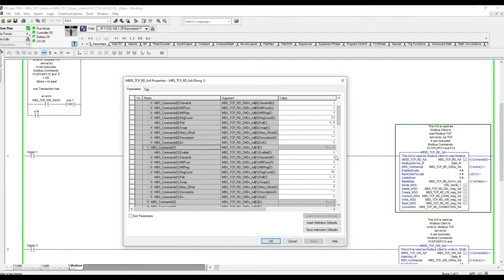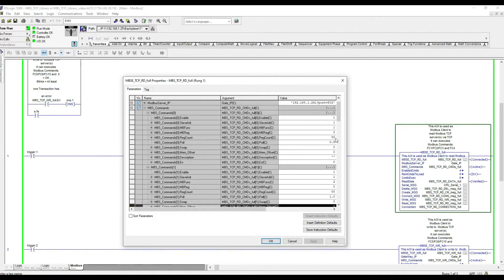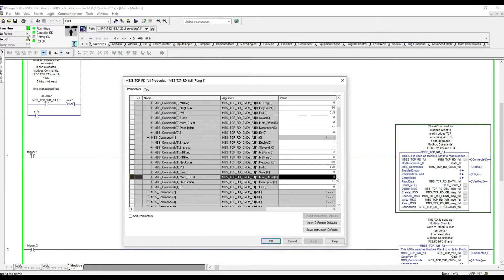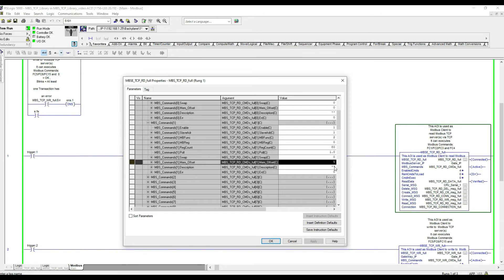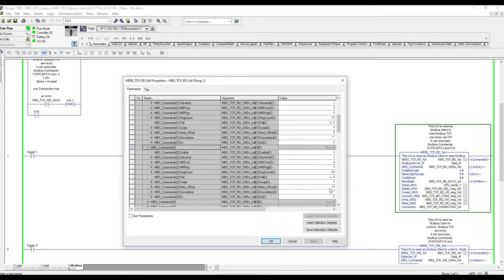The next command is function 2, reading 80 input statuses. We start from element 5 in the 120-register array because the 80 coils occupy 5 registers — each register has 16 bits, so 80 coils fill the first 5 registers (elements 0 to 4). This command will also occupy 5 registers for the 80 input statuses.